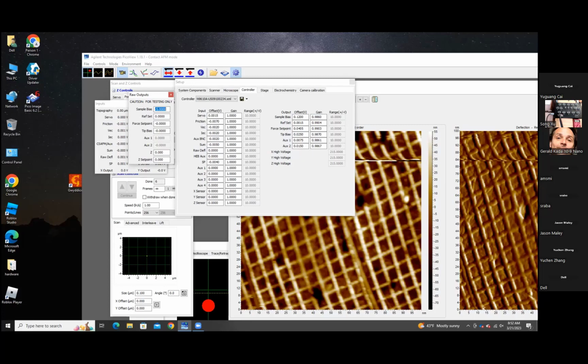Once you've done the positive 5 and negative 5, you want to also output positive 10 volts and negative 10 volts and check both of those. What you'll find is it's probably going to be 10.01. Let's try that. Positive 10 volts on the sample bias. Is plus minus 10 volts the limit, right? Yes, that is the limit.